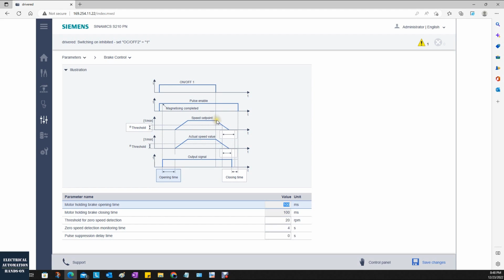And once we stop the motor, at this dash line here, we turn off the motor power. Once we turn off the motor power, by the inertia the motor may still spin, and the speed slows down. Then we need to look at this threshold here. The threshold will monitor the actual speed. So once the speed is lower than this threshold, it will monitor this closing time, and then the brake will turn on to hold the motor.